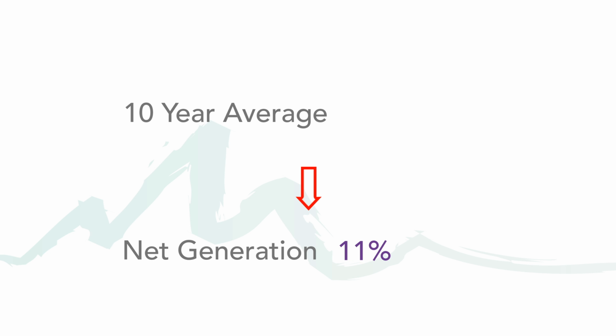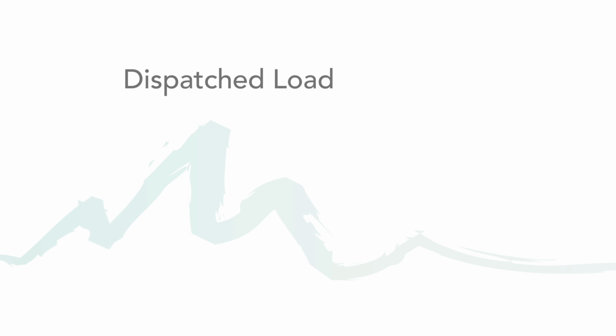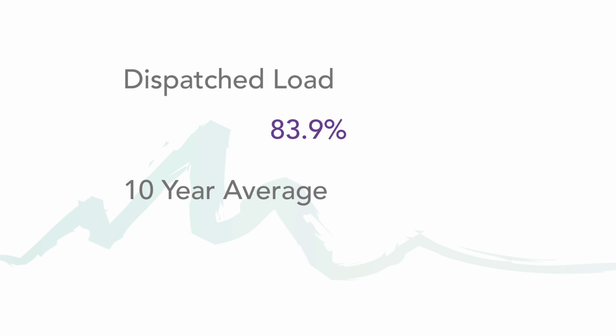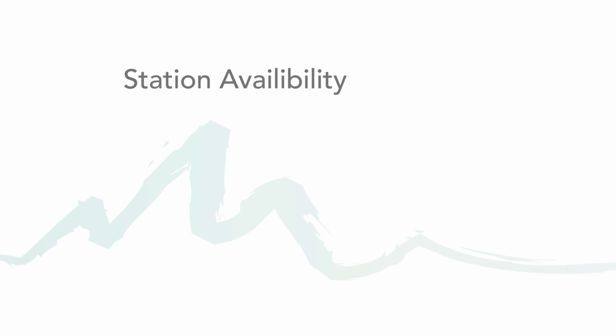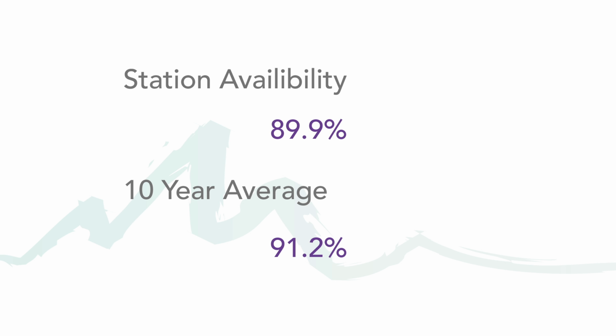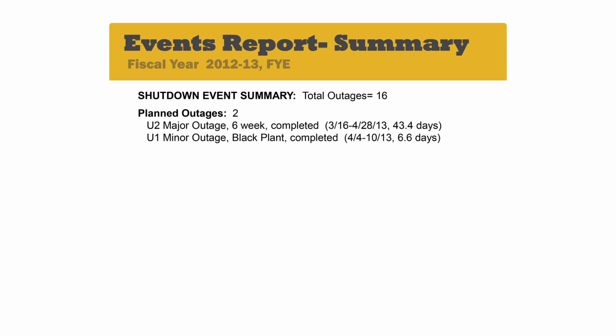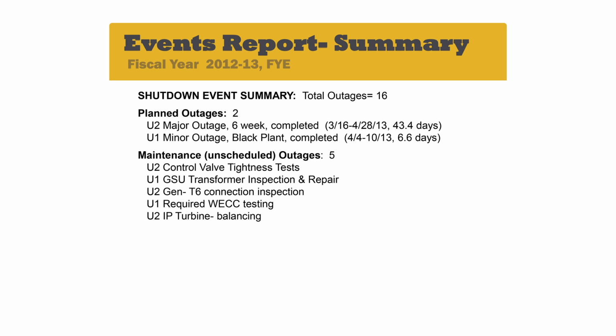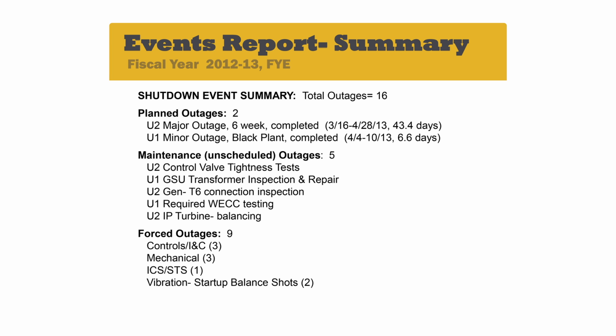The biggest impact on why these numbers are down 11% on net generation from the 10-year average is net output factor or dispatched load, which is 83.9% with a 10-year average of 93.1%, down 9.2%. The remaining difference is in station availability of 89.9%, with a 10-year average of 91.2%, down 1.3%. The shutdown event summary shows 16 total outages, with 2 planned outages, 5 unscheduled maintenance outages, and 9 forced outages.